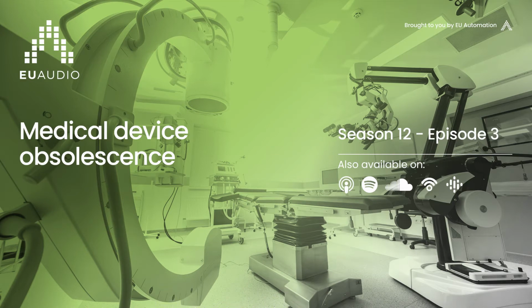Out with the old. In the past, problems have arisen with medical devices holding CE marks caused by parts failing during the expected lifespan of the device, and there then being a difficulty to replace the part in question. These issues, among others, highlighted the need for the regulations in place to be updated to include regular testing of equipment, regardless of whether it is certified with a CE mark.